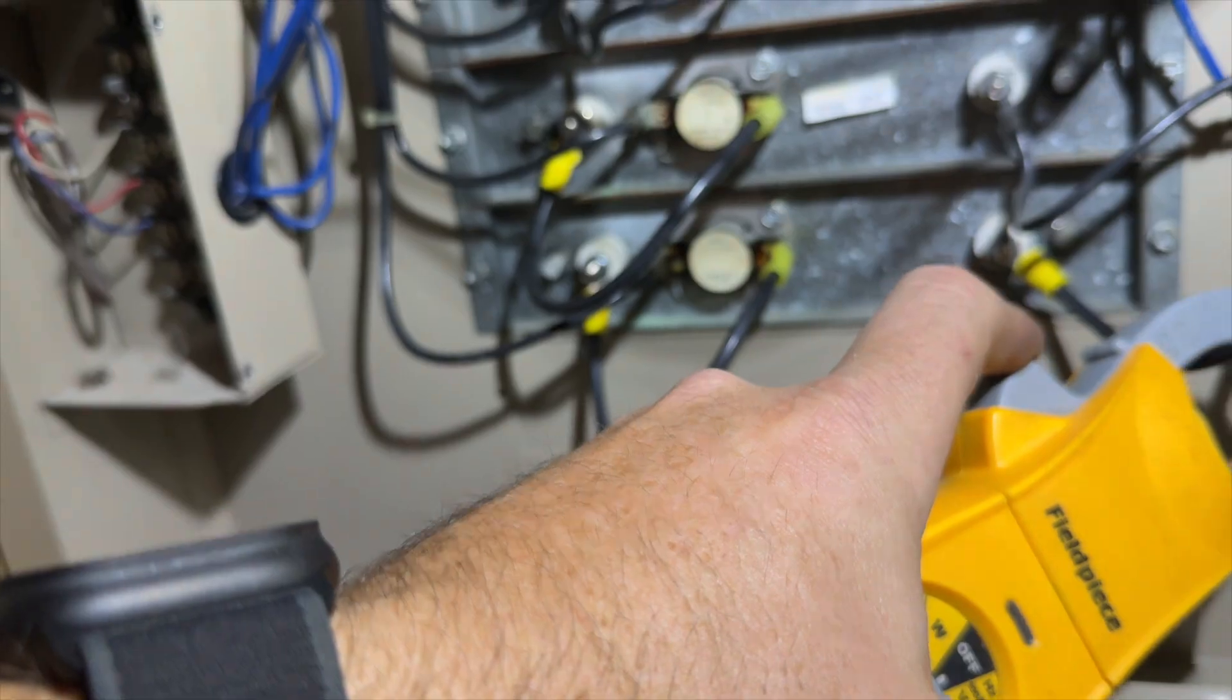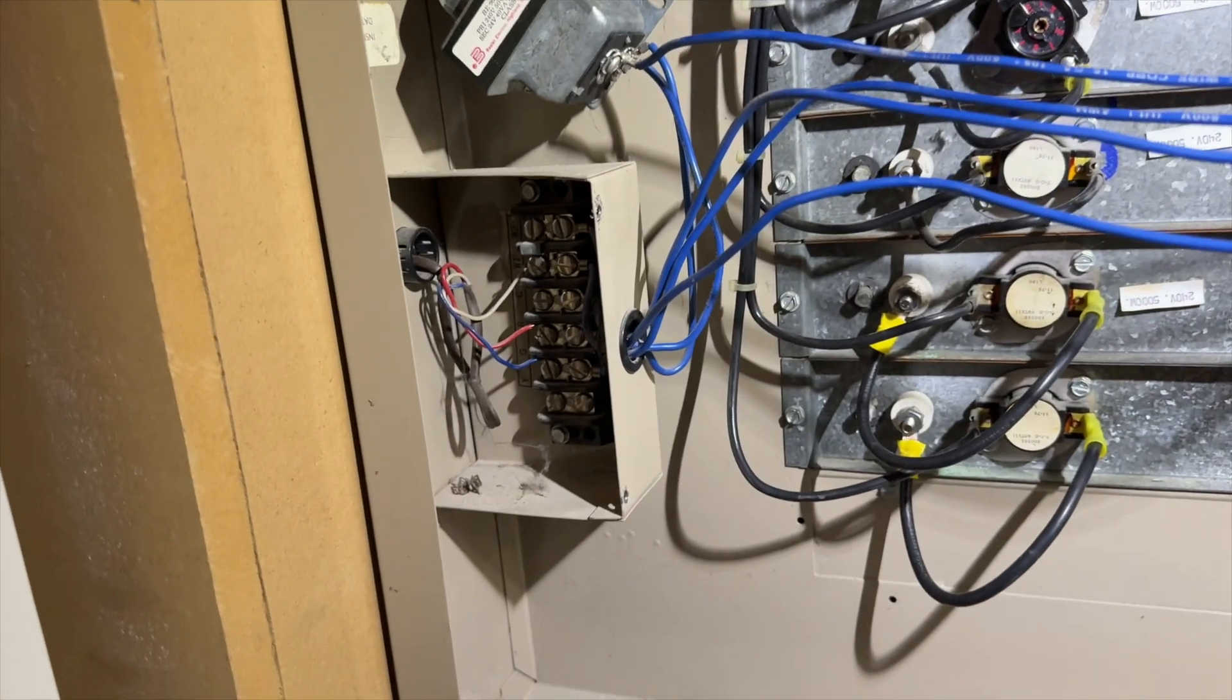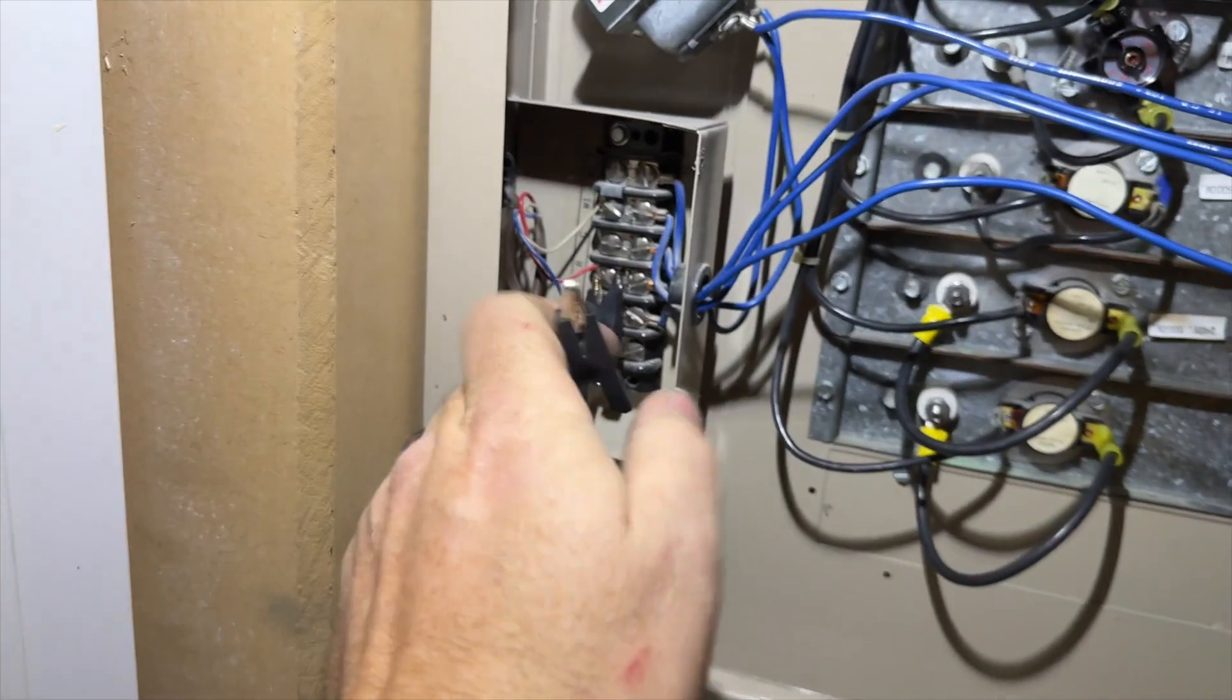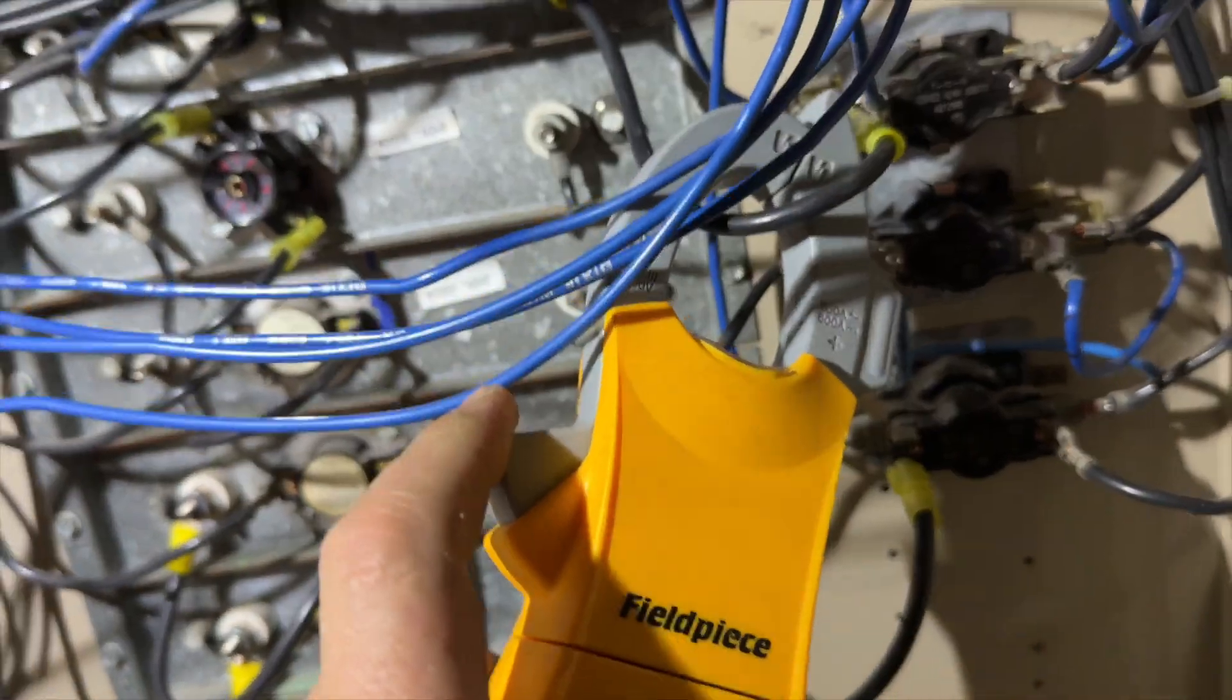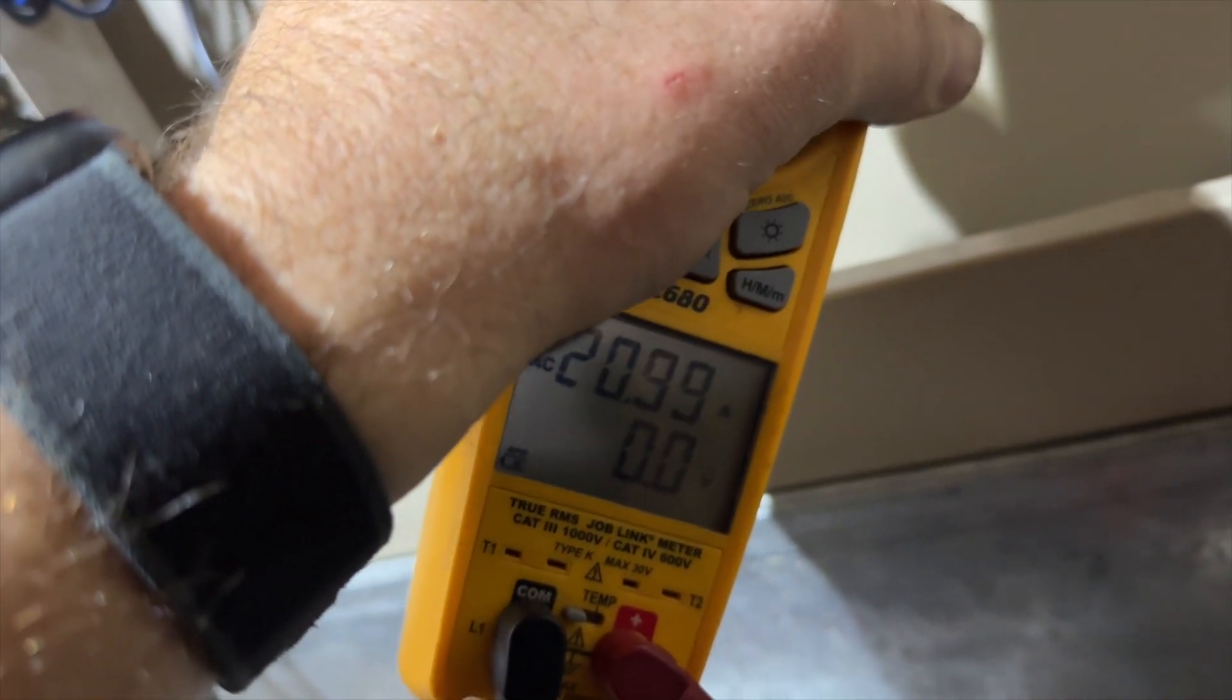Alright, let's call for fan first, see what happens. Okay, so we got fan. Fan relay right now. This is good. Alright, we're going to call for W1. Okay, so first one is on. Second one. Third one, it's on.